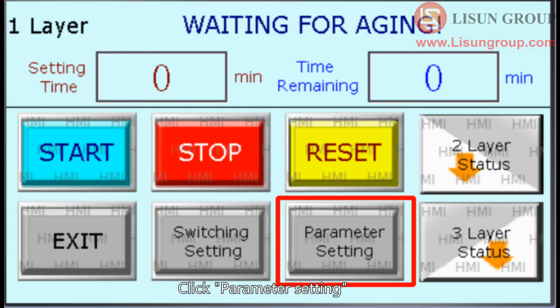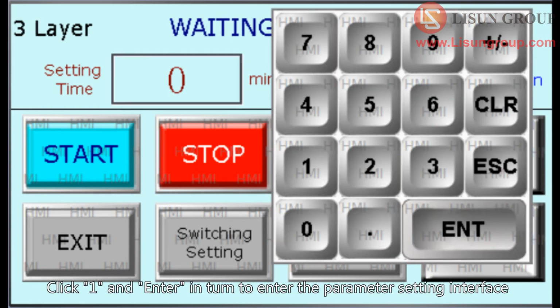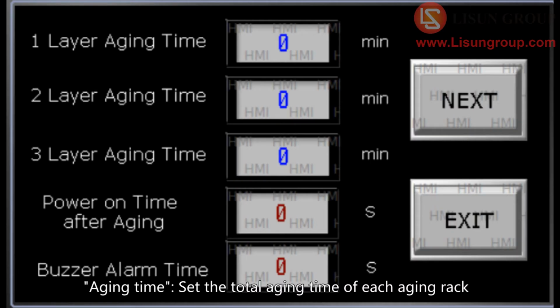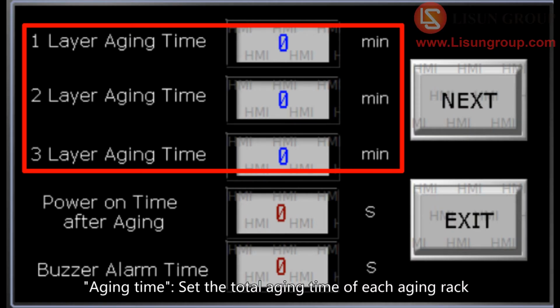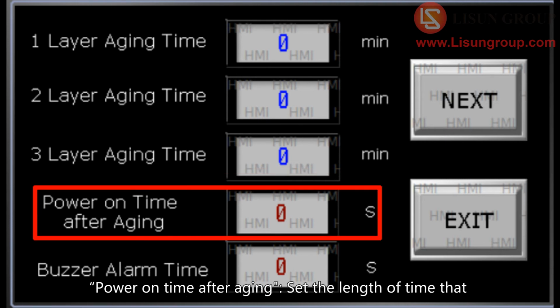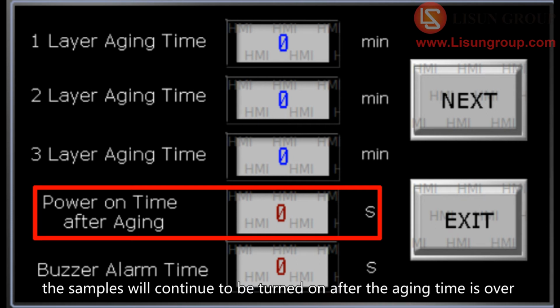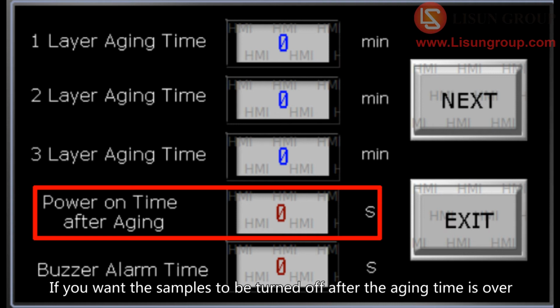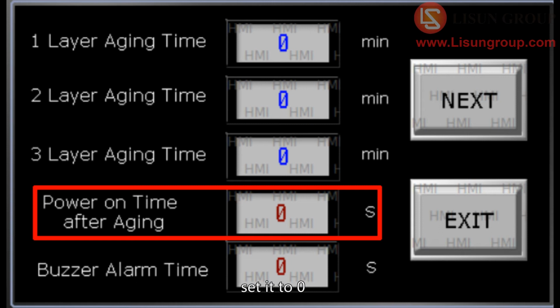Click Parameter Setting. The password is 1. Click 1 and enter in turn to enter the parameter setting interface. Aging time. Set the total aging time of each aging rack. Power on time after aging. Set the length of time that the samples will continue to be turned on after the aging time is over. If you want the samples to be turned off after the aging time is over, set it to 0.